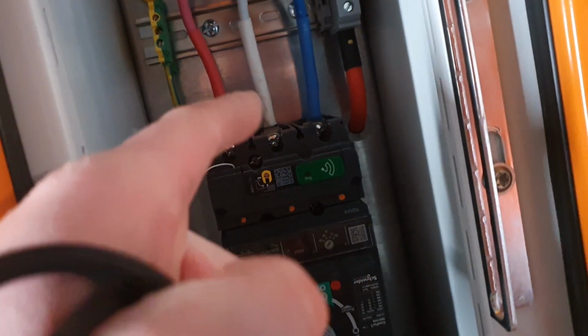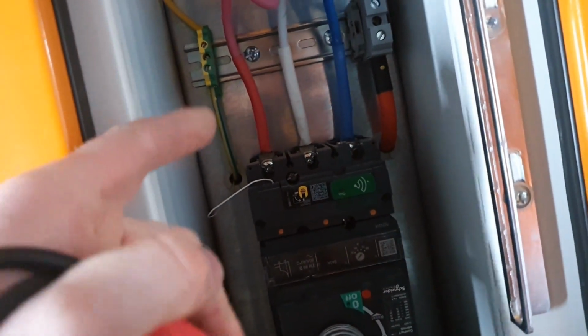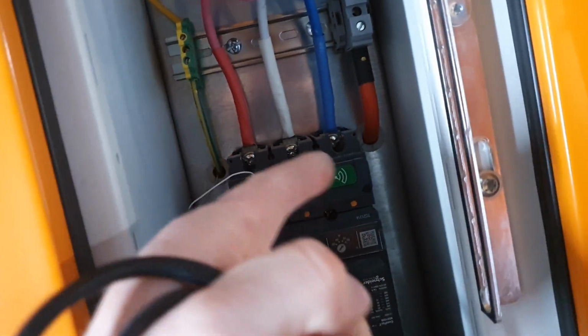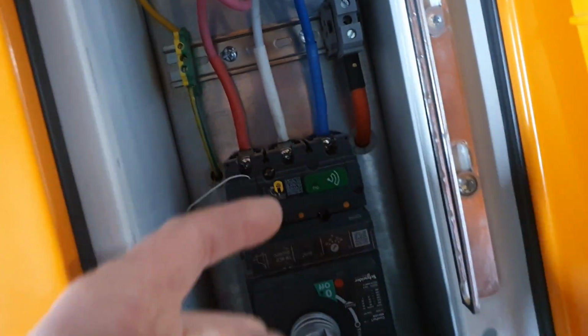And just to prove it, I disconnected all the tails and I had 500 mega ohms between. It's only to phases. If we do from earth to phase, it's completely clear, but phase to phase, you get this weird 8 mega ohm reading. So just a little tidbit for you guys.